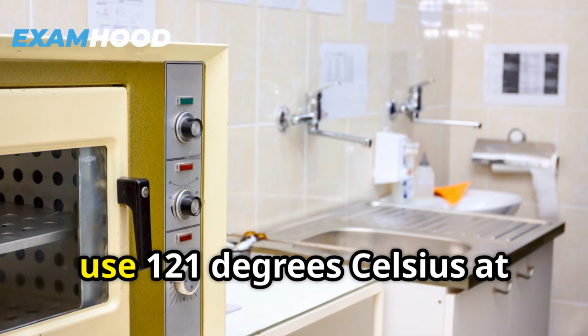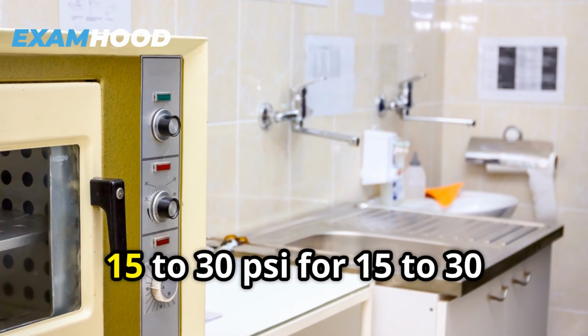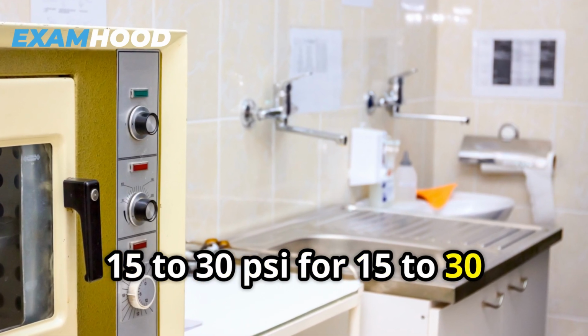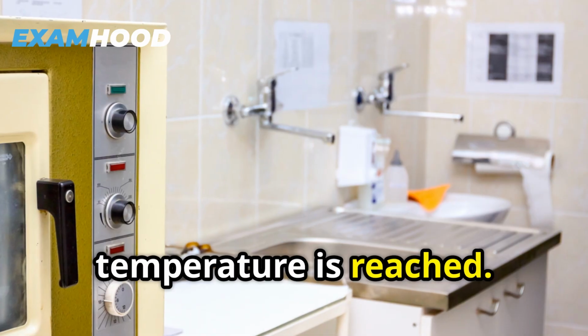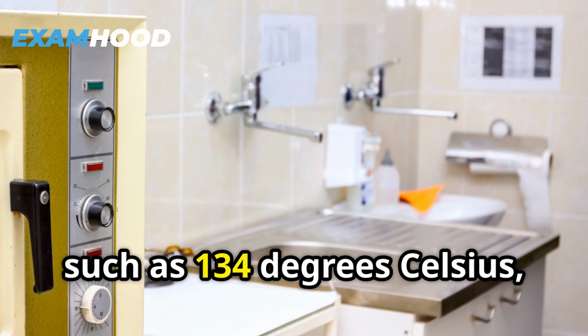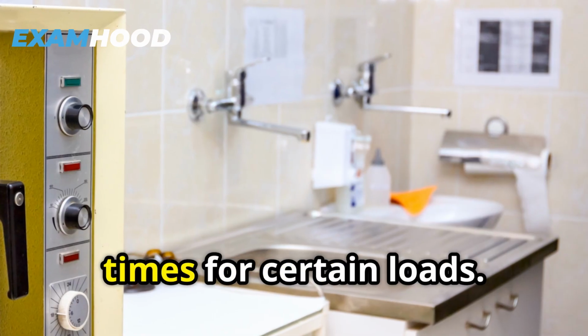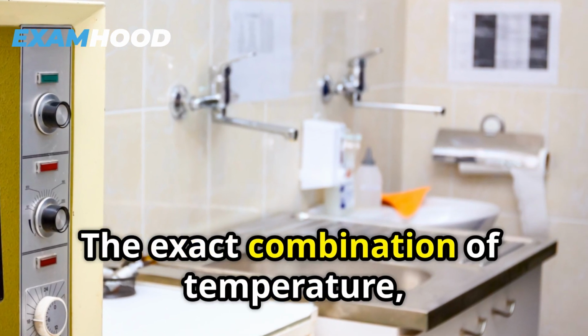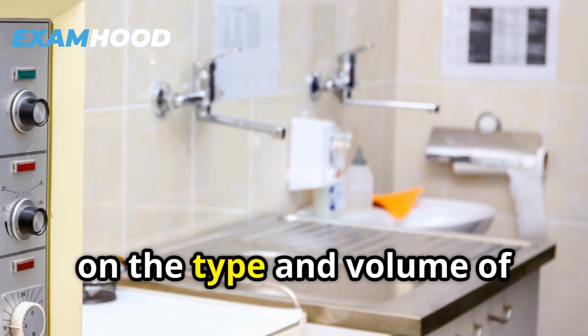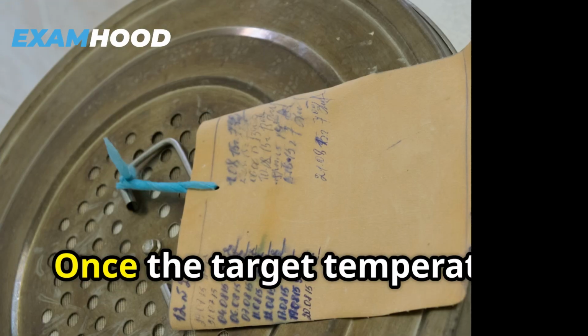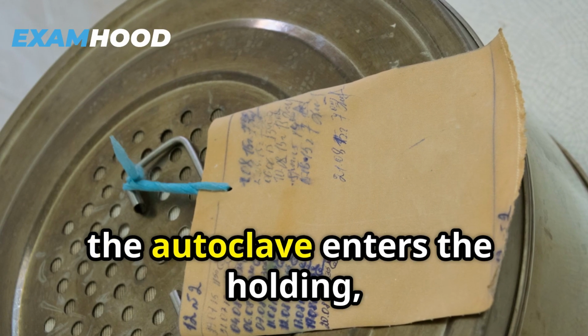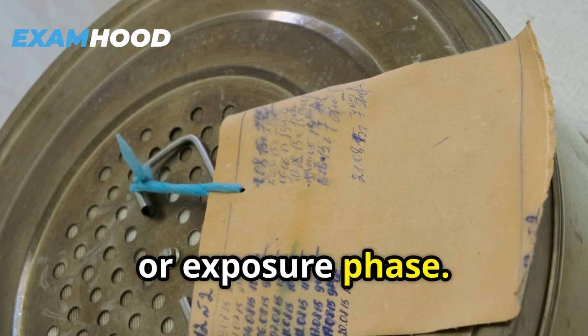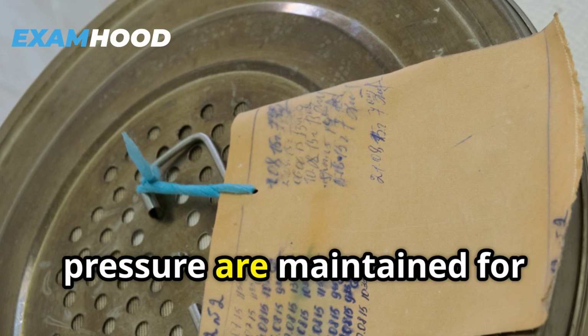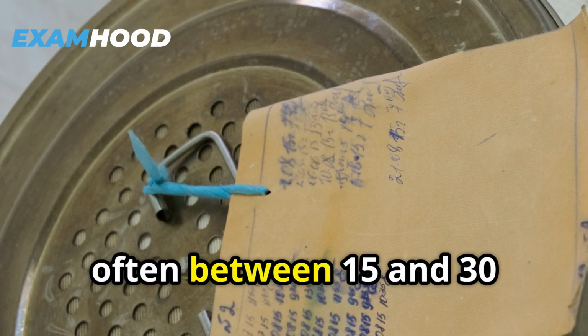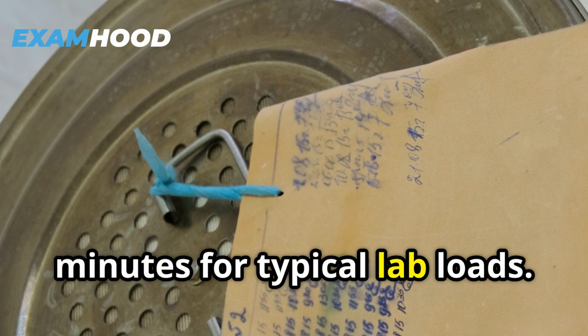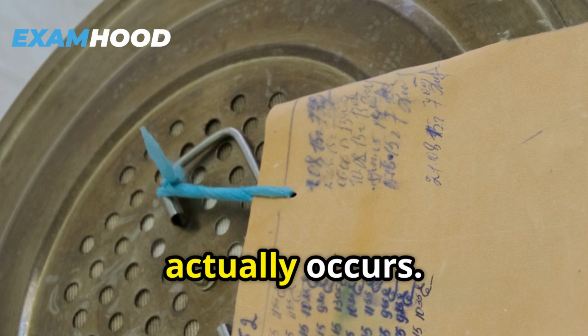Many laboratory protocols use 121 degrees Celsius at 15 to 30 psi for 15 to 30 minutes once the set temperature is reached. Higher temperatures, such as 134 degrees Celsius, allow shorter exposure times for certain loads. The exact combination of temperature, pressure, and time depends on the type and volume of material being sterilized. Once the target temperature and pressure are reached, the autoclave enters the holding or exposure phase. During this time, the temperature and pressure are maintained for a set duration, often between 15 and 30 minutes for typical lab loads. This is when sterilization actually occurs.